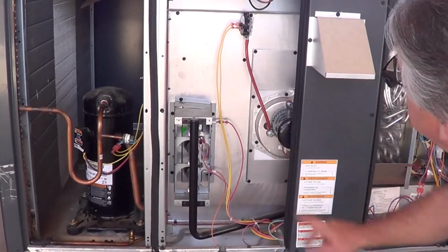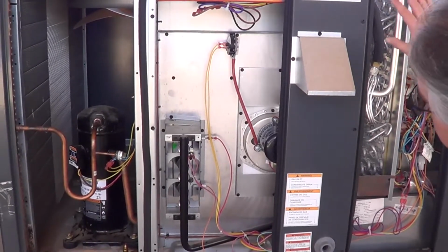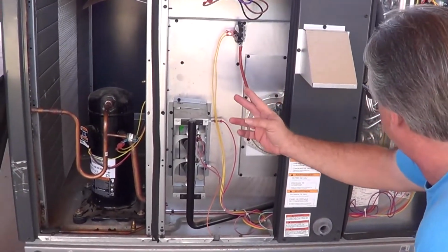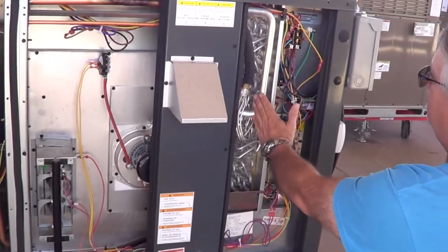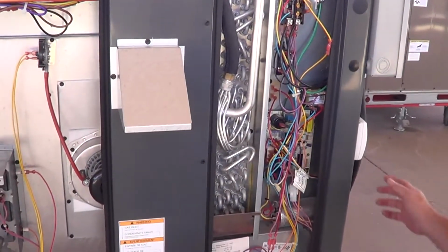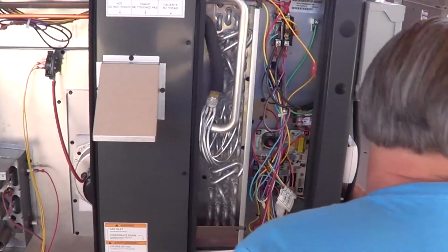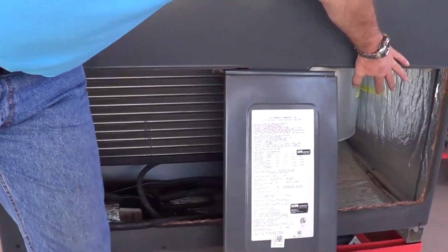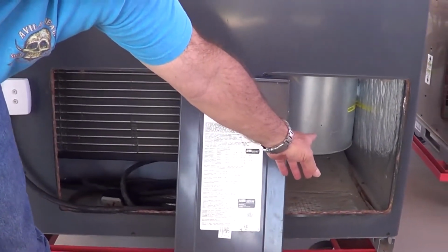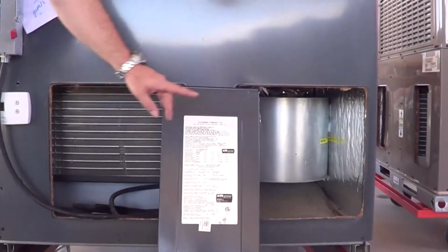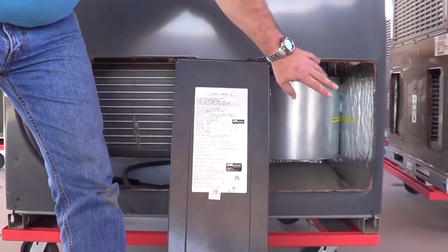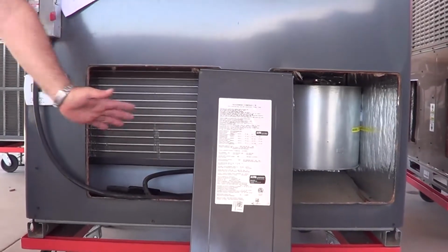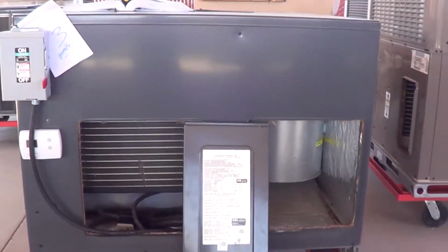heat exchanger behind this wall, and the indoor fan motor on the other side of the machine blows the air from the return air duct through the heat exchanger and then across the evaporator of the cooling side of the air conditioner and around over here to the supply air duct. So if you look around over here, you can see this would be our supply air, and this is our return air. You can see the indoor fan located there in the return air side of the machine. It's sucking air in this way, blowing it across the heat exchanger, and then the air is forced across the evaporator, and into the building through the supply air duct.